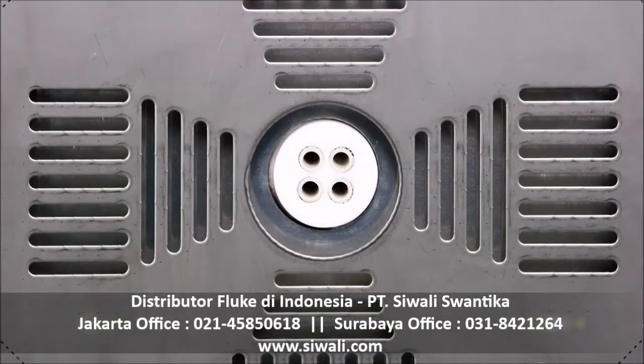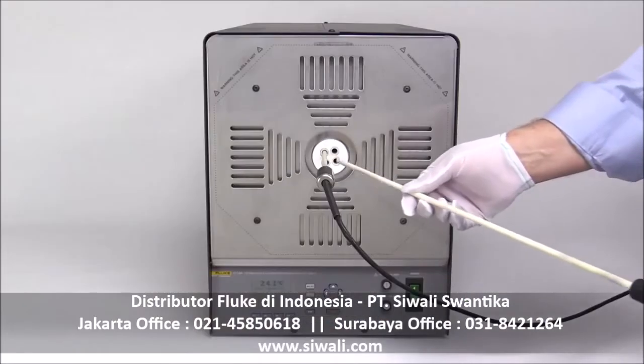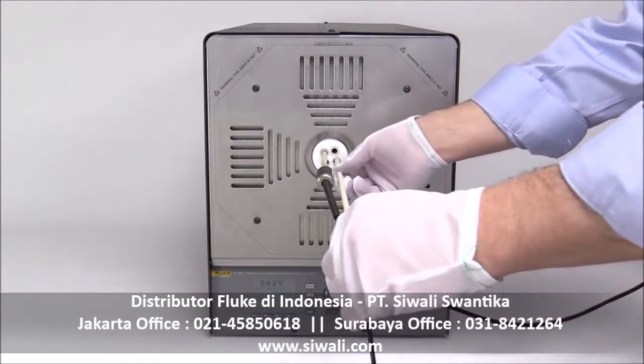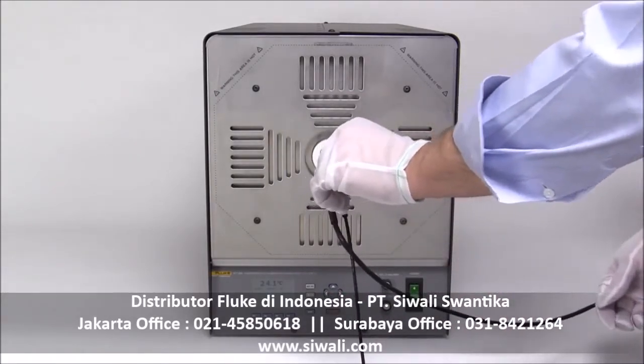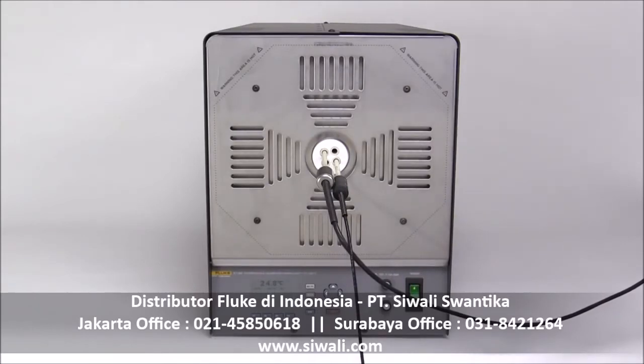The 9118A with an isothermal block improves heat transfer and stability. This configuration better equalizes the temperature between the reference probe and the unit under test, which lowers measurement uncertainty compared to a calibration without a block.